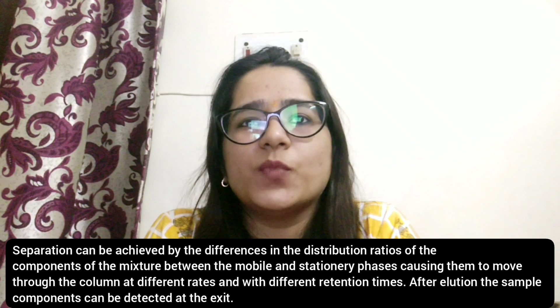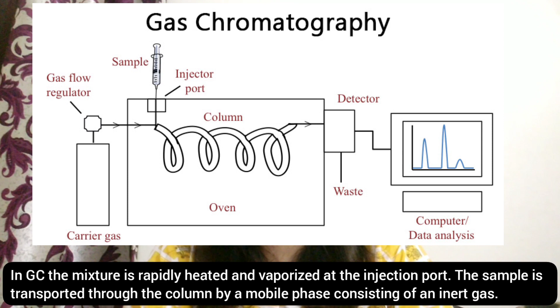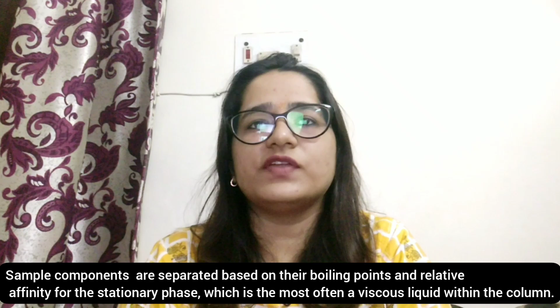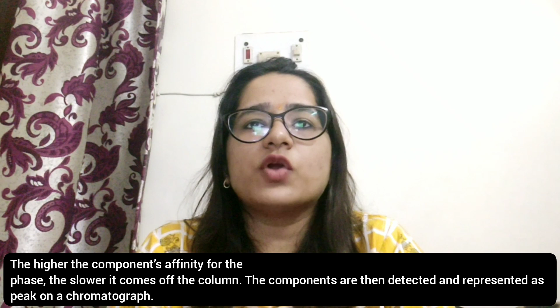In gas chromatography, the mixture is rapidly heated and vaporized at the injection port. The sample is transported through the column by a mobile phase consisting of an inert gas. Sample components are separated based on their boiling point and relative affinity for the stationary phase, which is most often a viscous liquid within the column. The higher the component's affinity for the phase, the slower it comes off the column. The components are then detected and represented as peaks on a chromatogram.